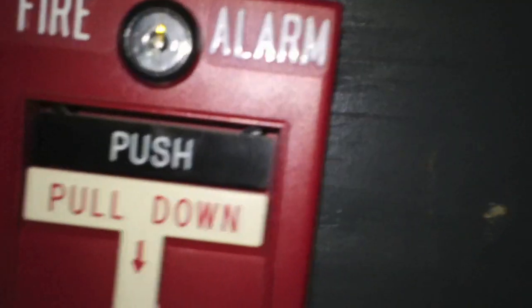Inside here, inside behind this sticker, and I do apologize about the light on my camera, it is very bright. Try to get this open. There we go. Right back there, there are dip switches that actually help program the address of this initiating device. This initiating device right now is currently set to 0, 0, 0. Is that set to 1? I think it's set to 1. I would have to look closely in order to actually understand which one it is. But that's actually how you program an addressable point, by setting the dip switches to the address and then programming the address to say what it actually is.